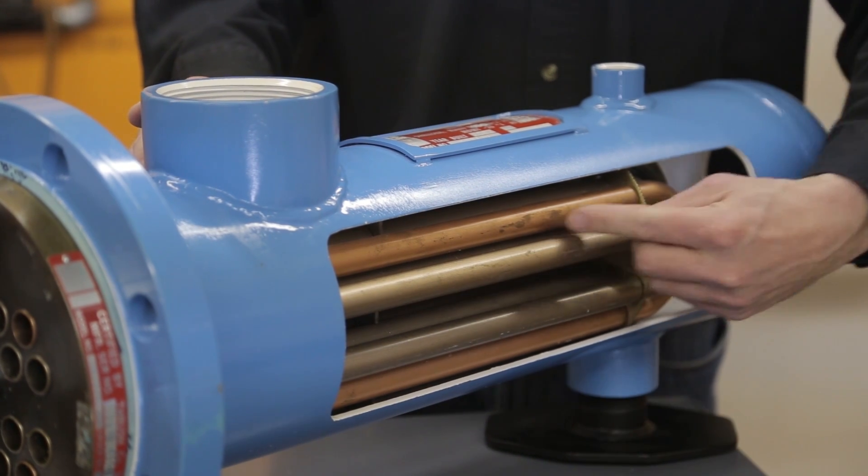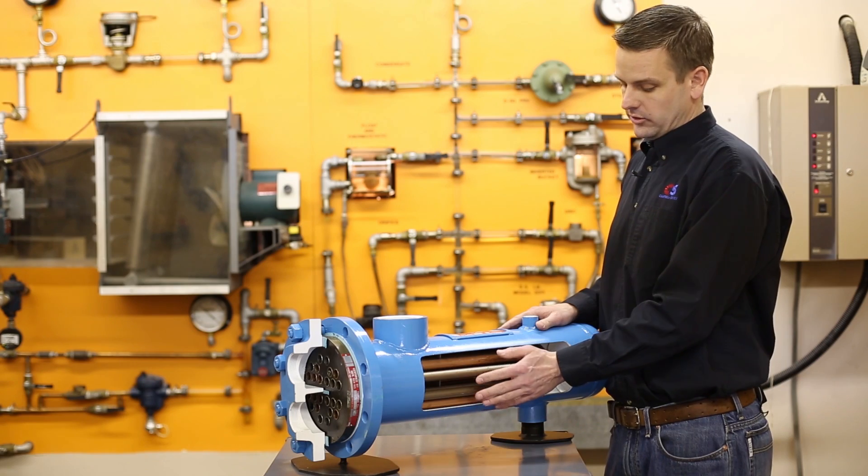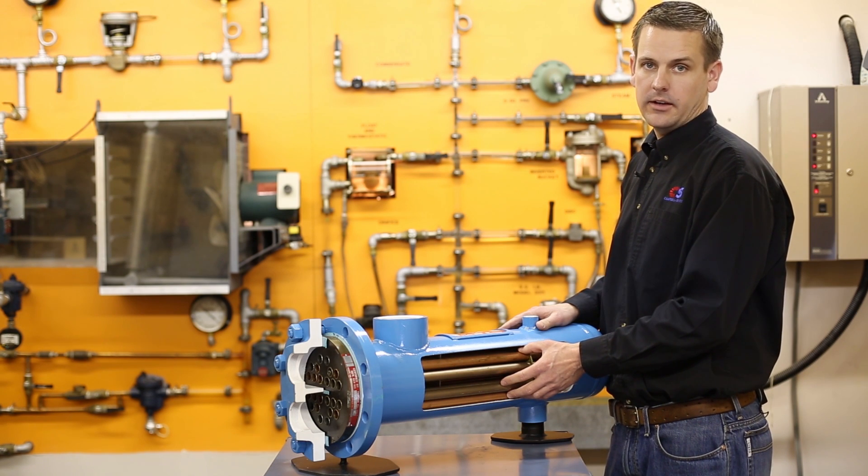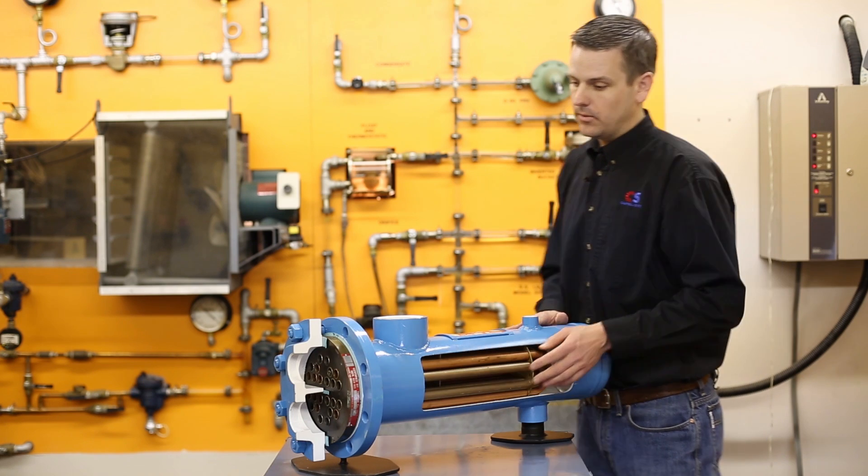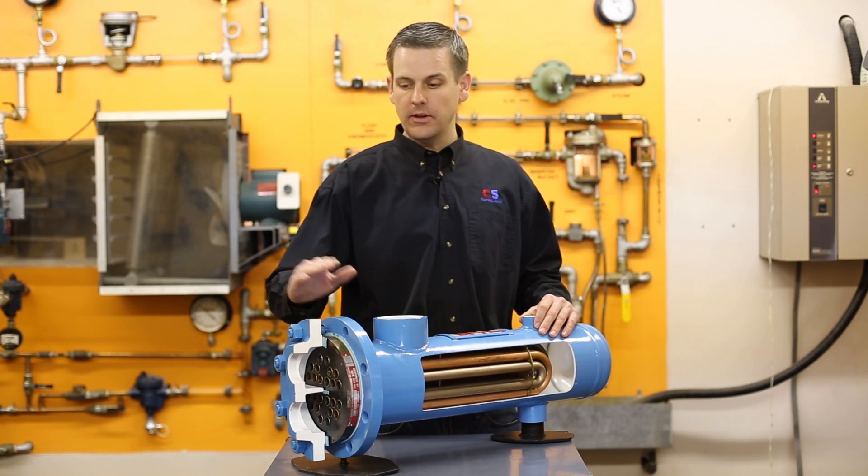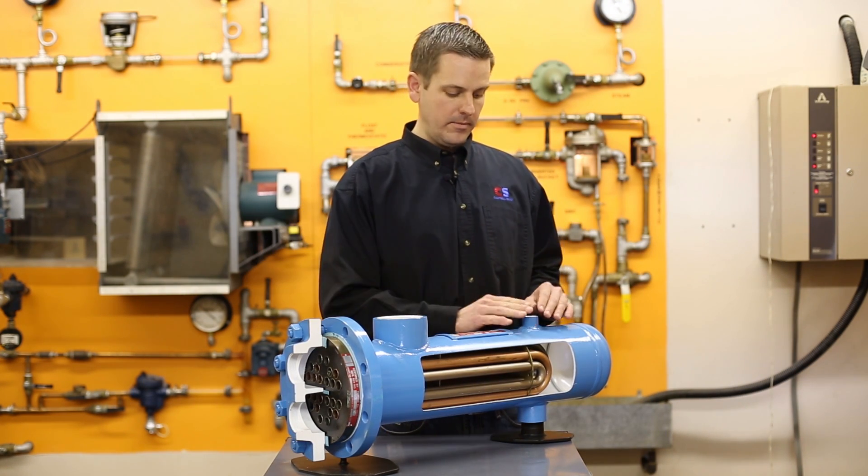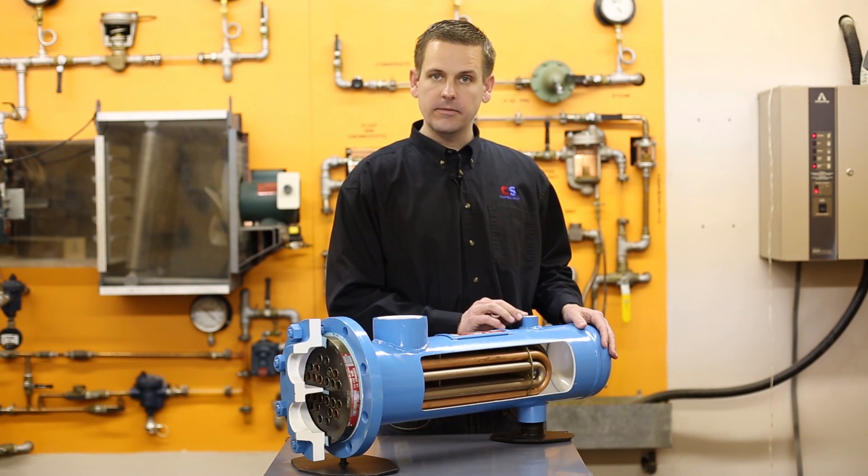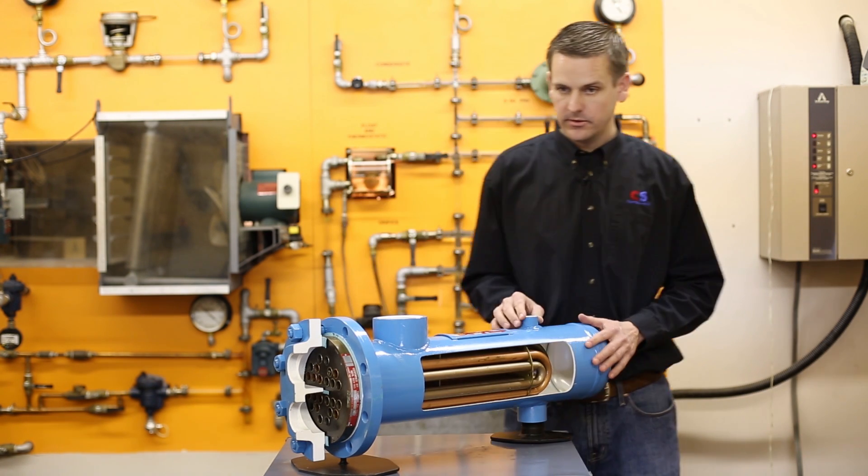Now when we do that, we have a unit full of air and non-condensibles. So when our steam control valve opens back up, we want to make sure we purge all that out with the air vent. Again, we put an air vent and a vacuum breaker off of this fitting.